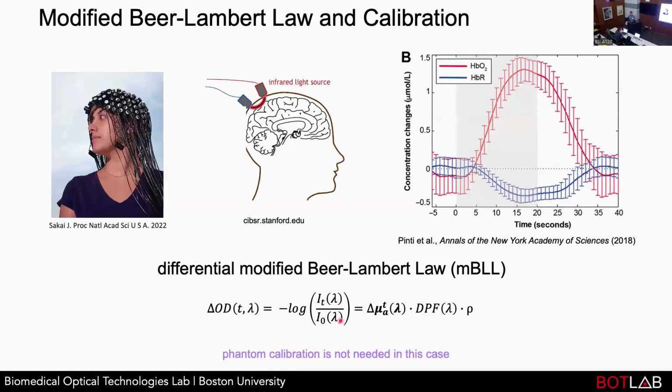You also might ask, how do I get the optical properties of this phantom? You can take a piece and do something like inverse adding-doubling, potentially. That's probably the closest to first principles. You can also use another phantom with known optical properties and use an instrument to measure a new phantom. That's probably what's used in practice a lot. That's what we've used in practice.